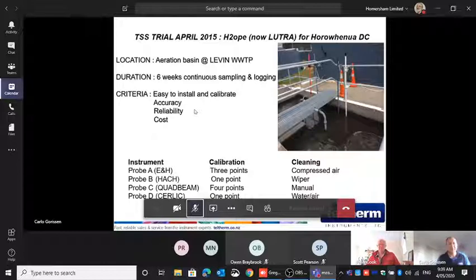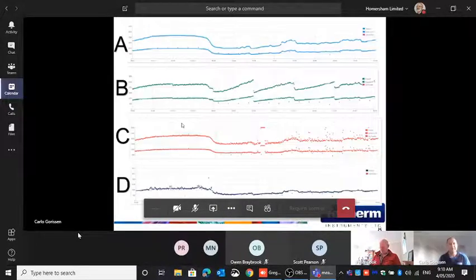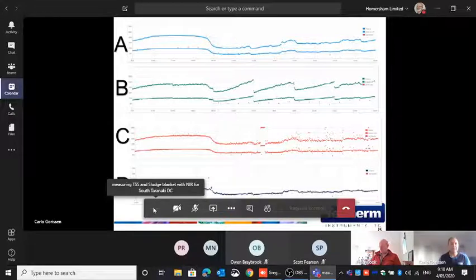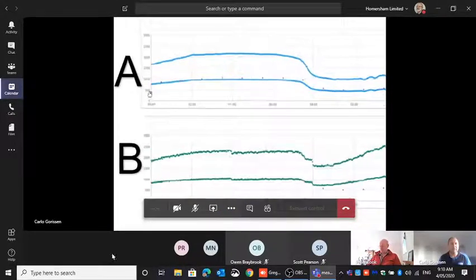So in 2015, the Horowhenua District Council did a trial for the TSS sensors in an aeration basin in Levin. Basically, we had an Endress+Hauser, the Hach, a quad beam, and our probe in one aeration basin at the same depth. And in the middle was a sampler that basically took a lab sample every so often. Here you see, if we go a little bit closer, these little red dots are actually the lab samples.